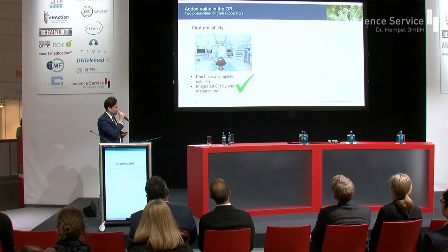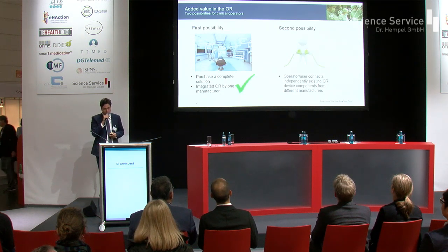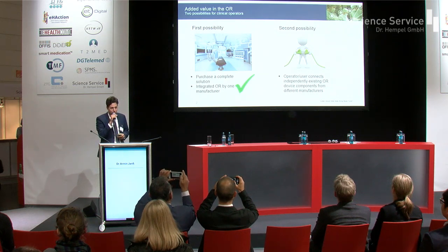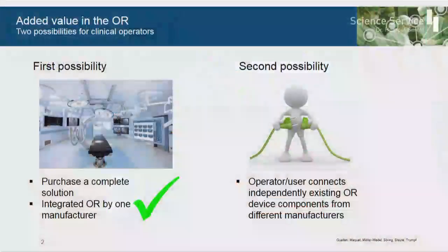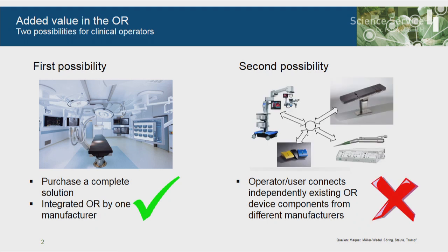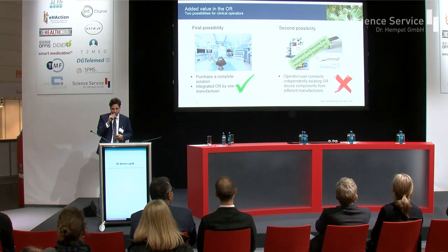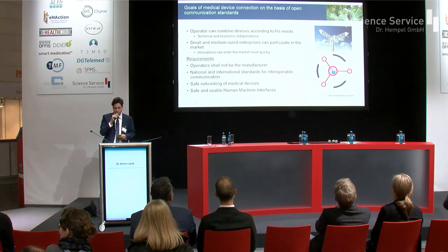And there's a second possibility, which is not really a possibility. If there's a clever IT technician in the hospital who would be able to connect different kinds of devices of different manufacturers, that is definitely not advisable, because then the clinical operator would become the manufacturer, and then he would become liable. So this is not advisable.